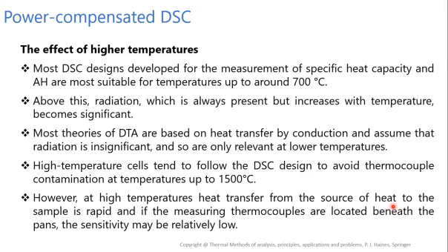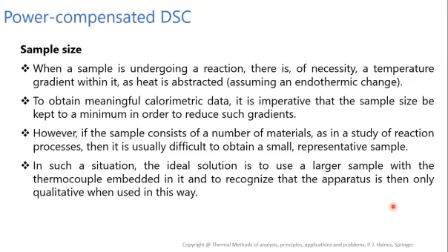Celsius. However, at high temperature, heat transfer from the source of the heat to the sample is rapid, and if the measuring thermocouples are located beneath the pans, the sensitivity may be relatively low. So that is why there is a much greater effect of higher temperature whenever we consider the DSC designs.